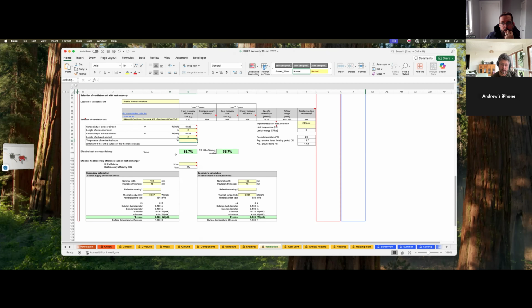And don't forget, it depends on what vent he's using. Normally you have 1.5 meters between the supply and exhaust vents. However, you can get a combined one, which would probably work in your design. They don't work very well if it's in a courtyard or something. I'll have a look. He sent me through everything. Exhaust valve, did you say?